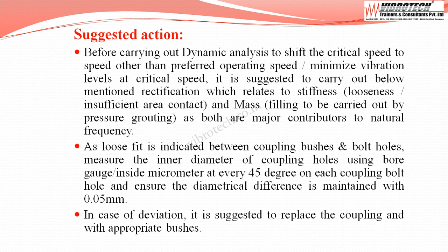As loose fit is indicated between coupling bushes and bolt holes, measure the inner diameter of coupling holes using a bore gauge or inside micrometer at every 45 degrees on each coupling bolt hole, and ensure the diametrical difference is maintained within 0.05 mm. In case of deviation, it is suggested to replace the coupling with appropriate bushes.